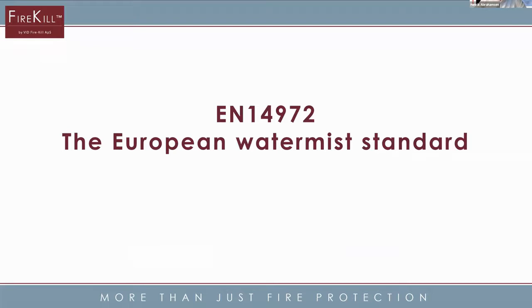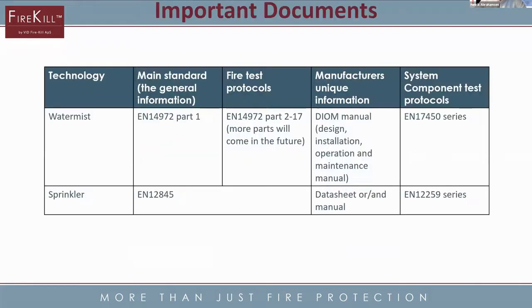EN 14972 is the upcoming European Watermist standard. We basically have some documents we have to relate to here. For sprinklers, you have the sprinkler bible, EN 12845, and some manufacturers' data sheets. For component testing, you have the EN 12259 series. For Watermist, it's a bit different. The main standard coming out is 14972 part one, which will basically contain how to install the system, like pumps and that sort of stuff.